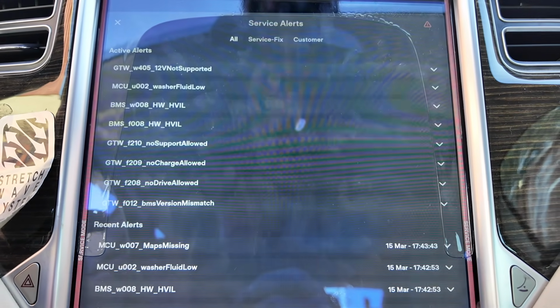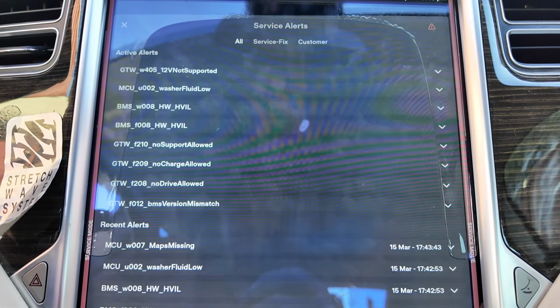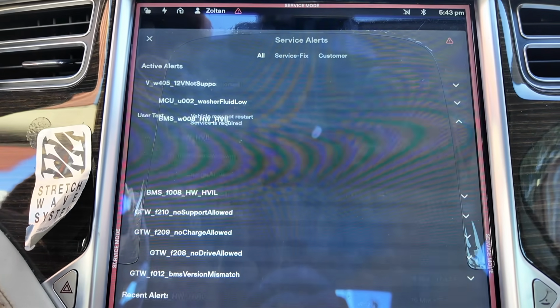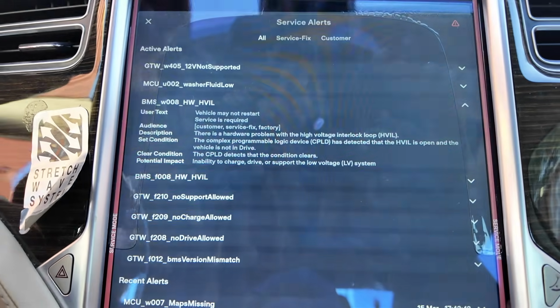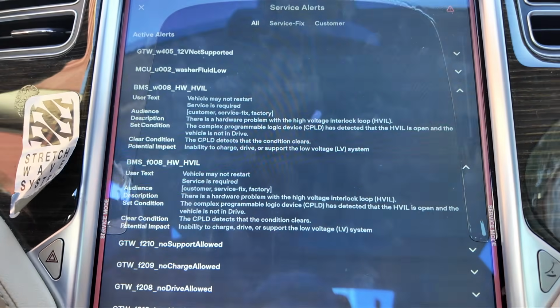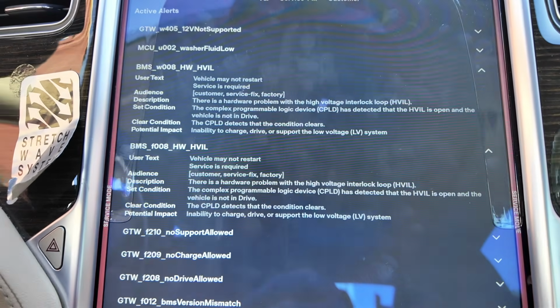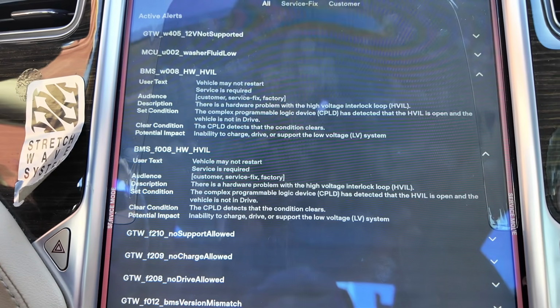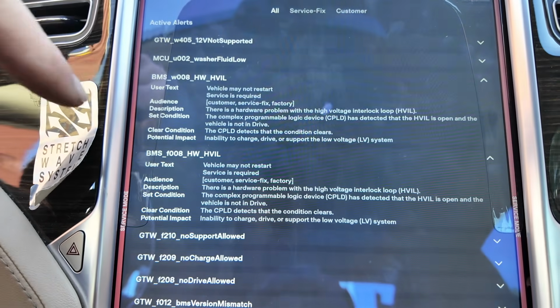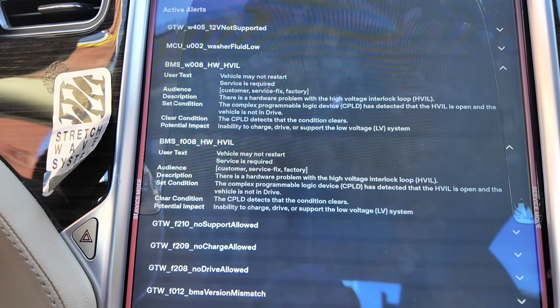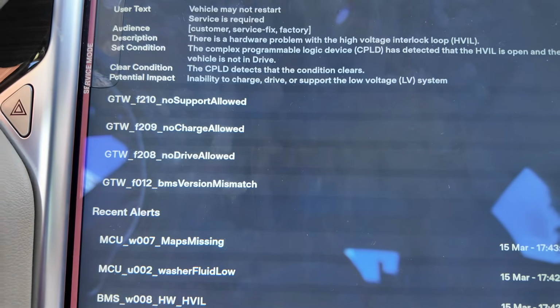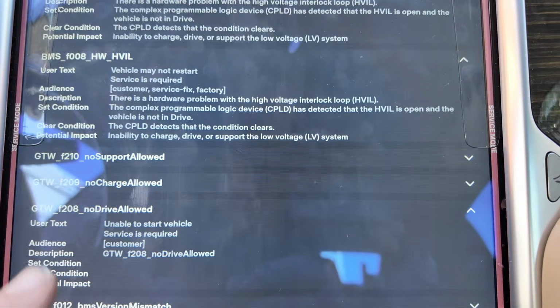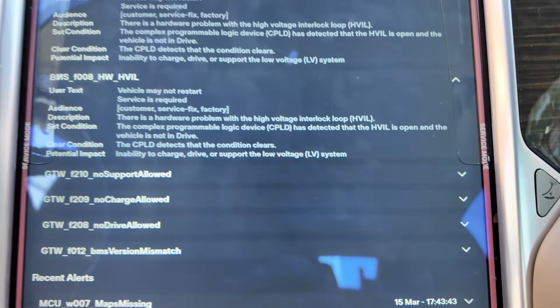So BMS version mismatch still, even though the part number is the same. Contactor fault is gone, but we still have HVIL. Still didn't clear. Amazing. So until HVIL is gone, we can obviously not even reprogram or run a software update.